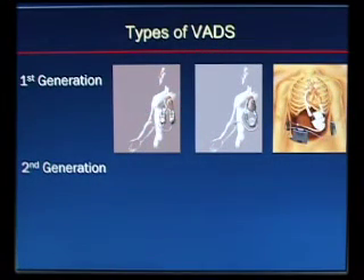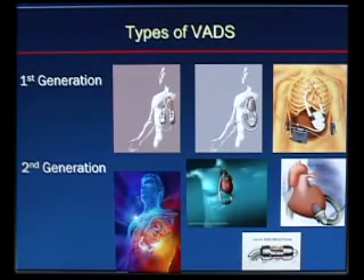The first generation devices are what we call pulsatile pumps or displacement pumps — the loud ones. They have a chamber that opens and fills with blood from the heart, then closes to eject into the aorta. A pump cycling 60 times a minute will eventually wear out, with mechanical parts brushing against each other and valves breaking down over time. The real breakthrough was the second generation device based on the Archimedes screw concept — a design over 2,000 years old. It provides minimal contact between parts, giving these devices much more longevity, and they're far more miniaturized because you don't need a pumping chamber.